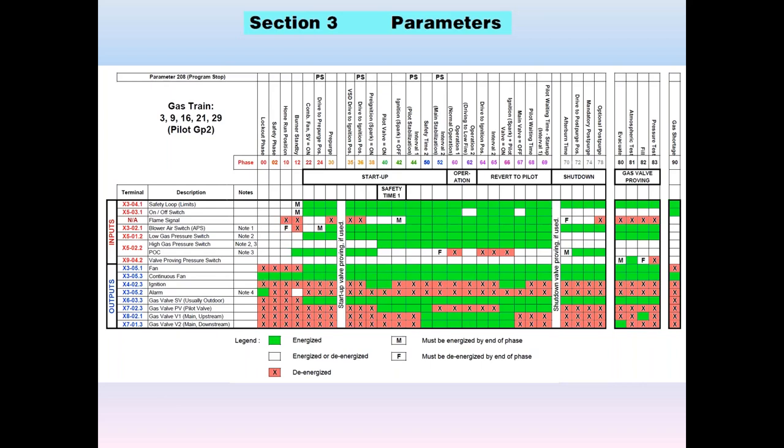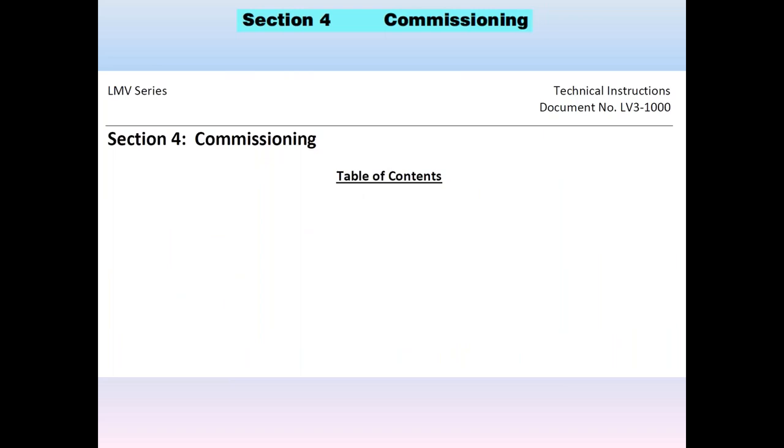The LMV3 can be put into a program stop using parameter 208. We can halt the LMV3 during pre-purge phase 24, or the ignition position phase 36. Then we can hold it during pilot or during the main, so that we can make adjustments to gas pressure and to the air and fuel settings.